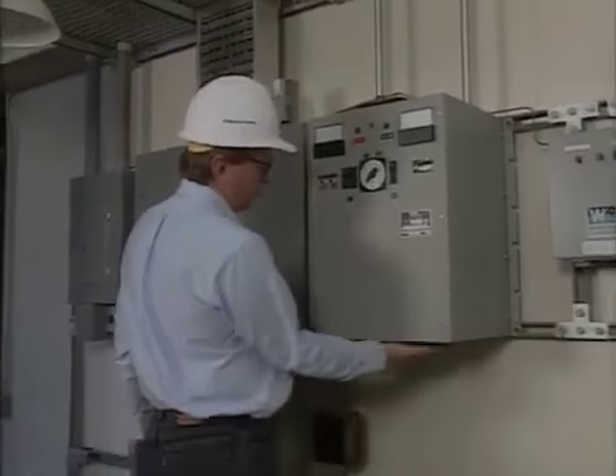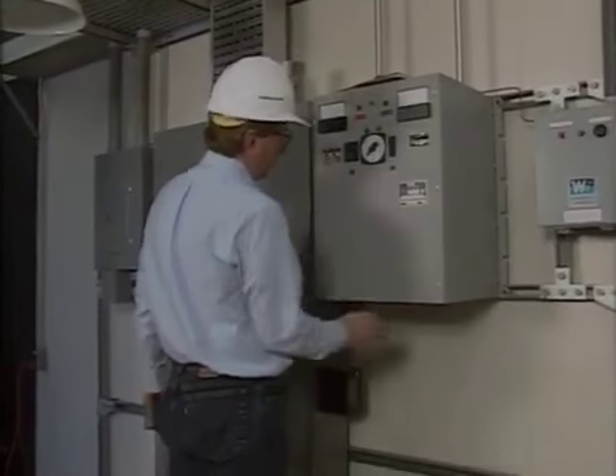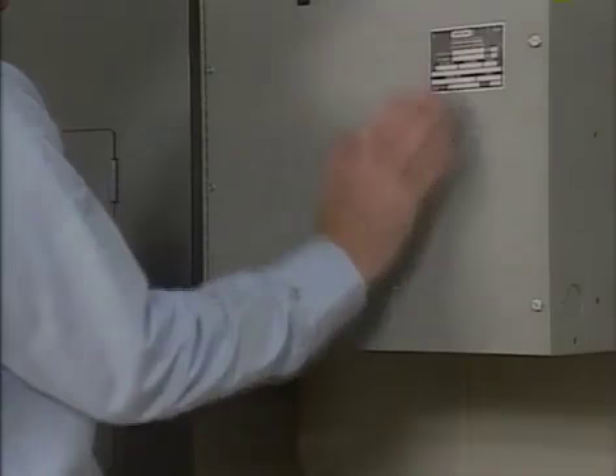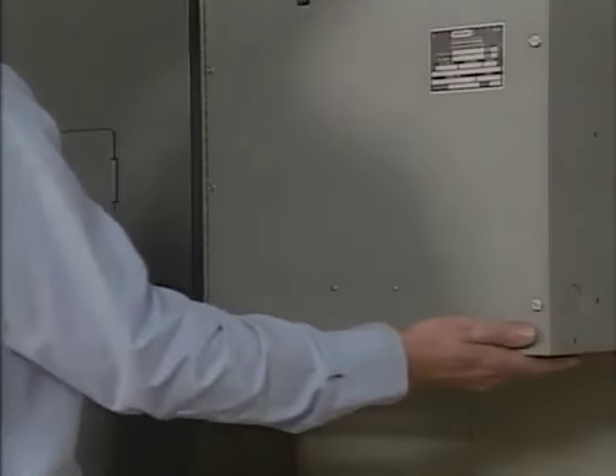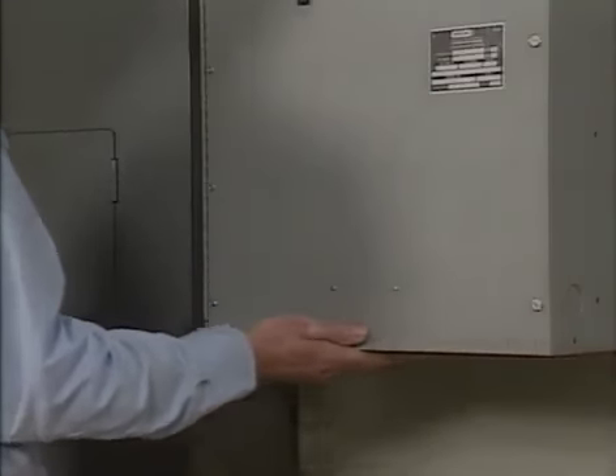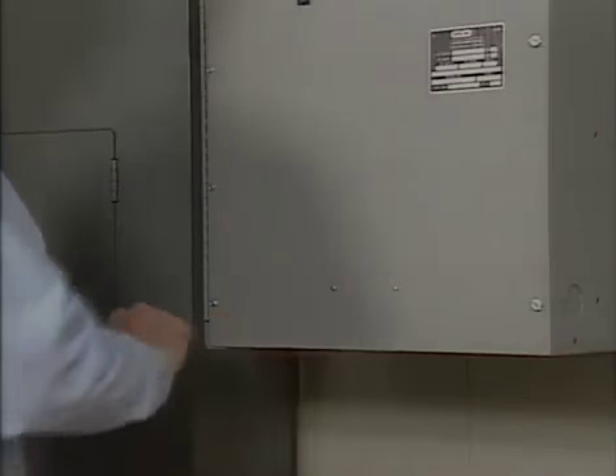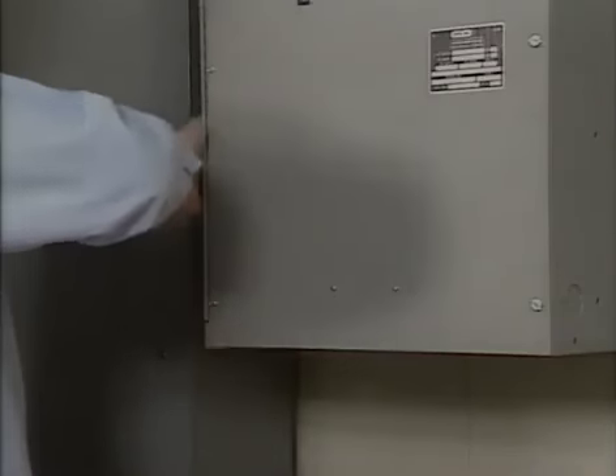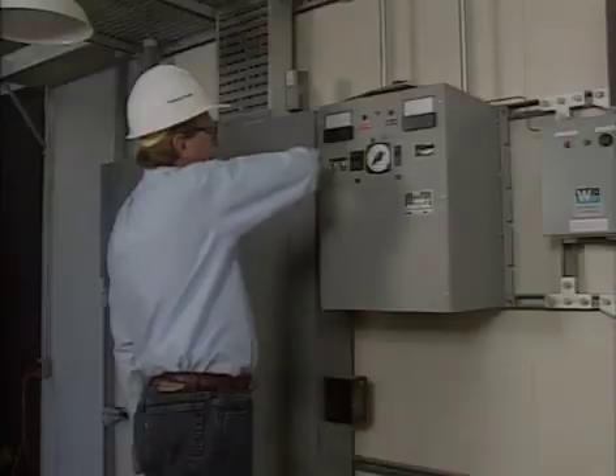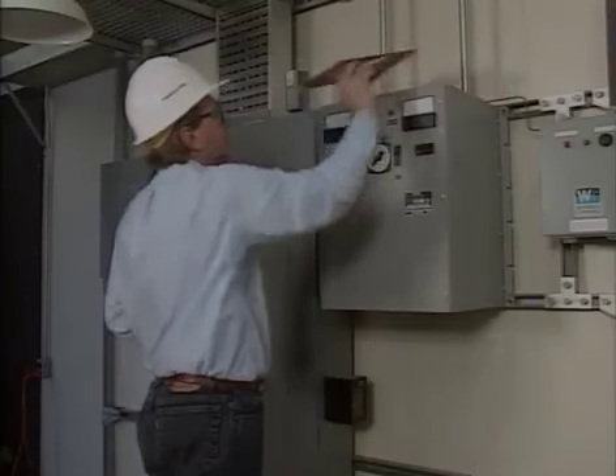A good place to begin is to check the charger for signs of excessive heat. The outside of the charger can be felt to determine if the charger is too hot. Excessive heat may indicate faulty internal components, poor internal connections, or poor ventilation. Excessive heat can result in charger failure.